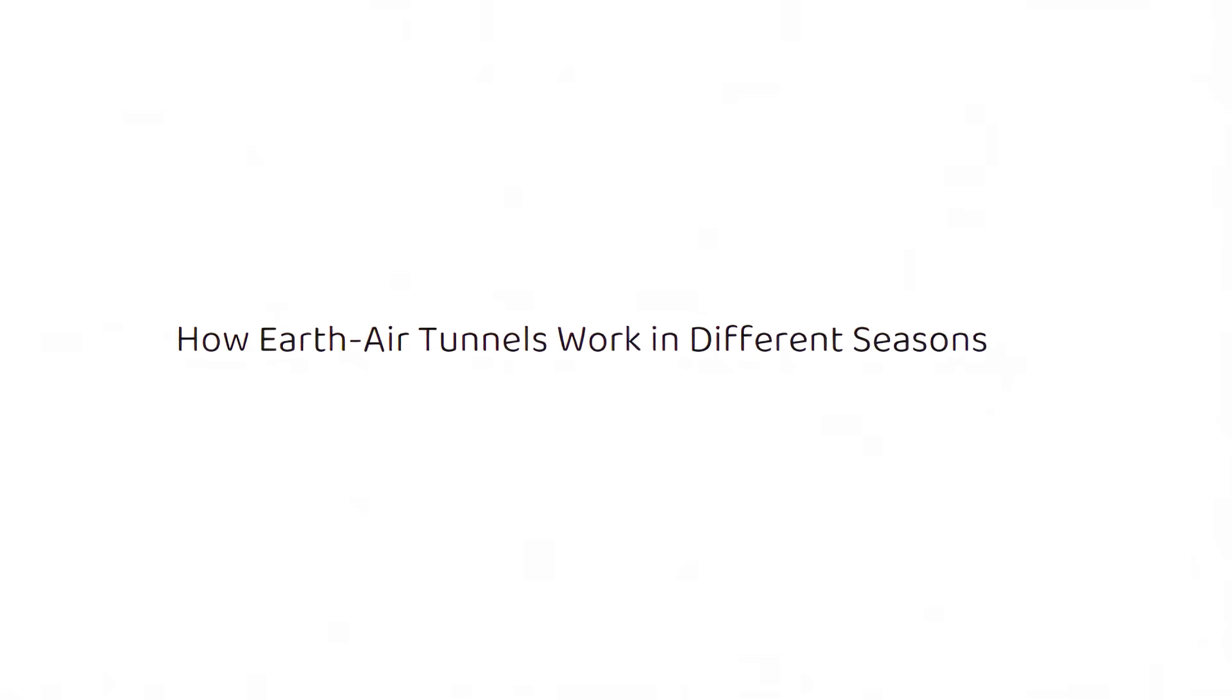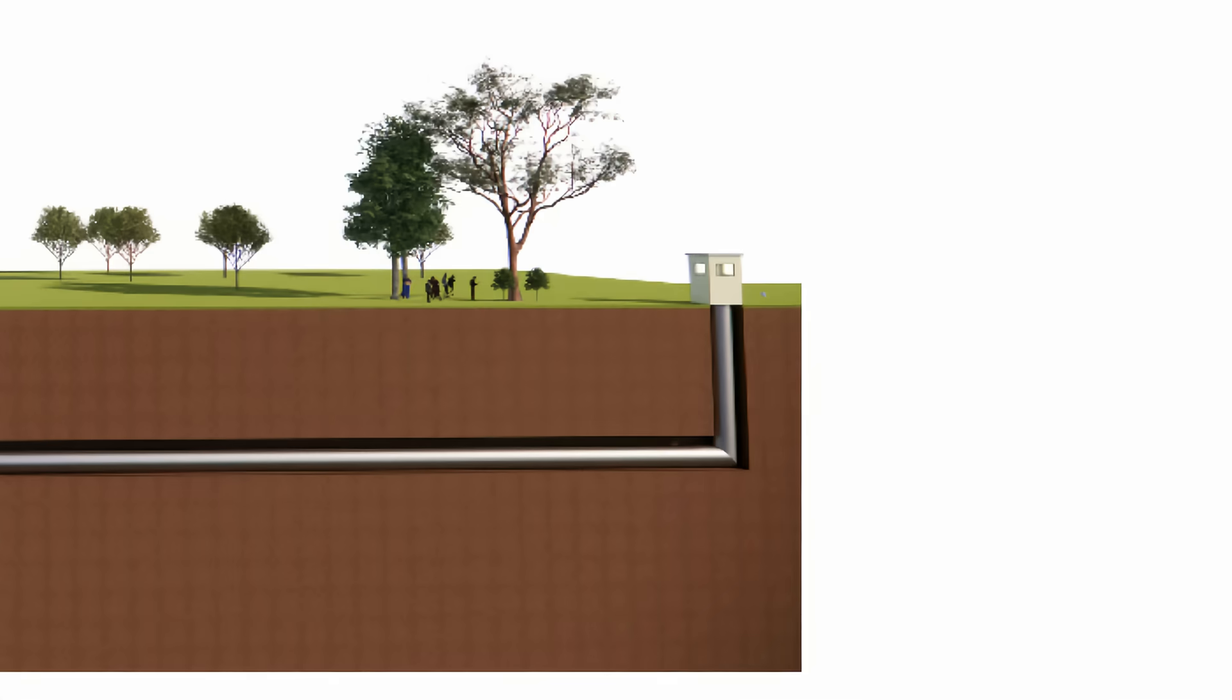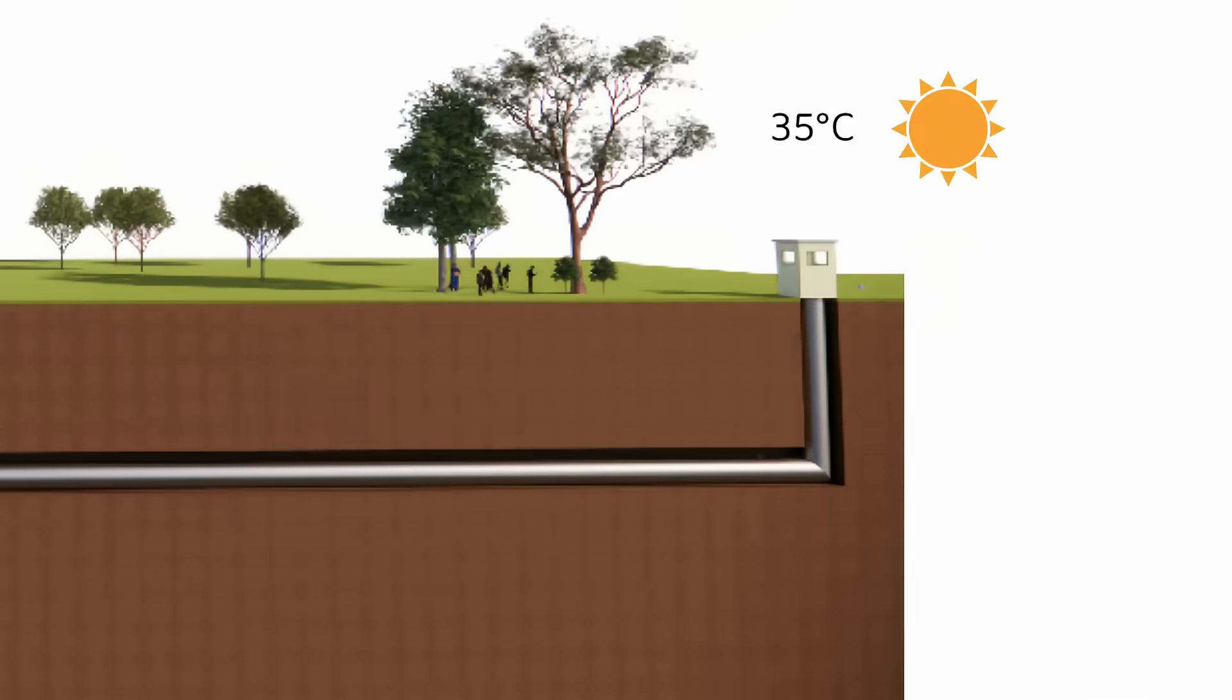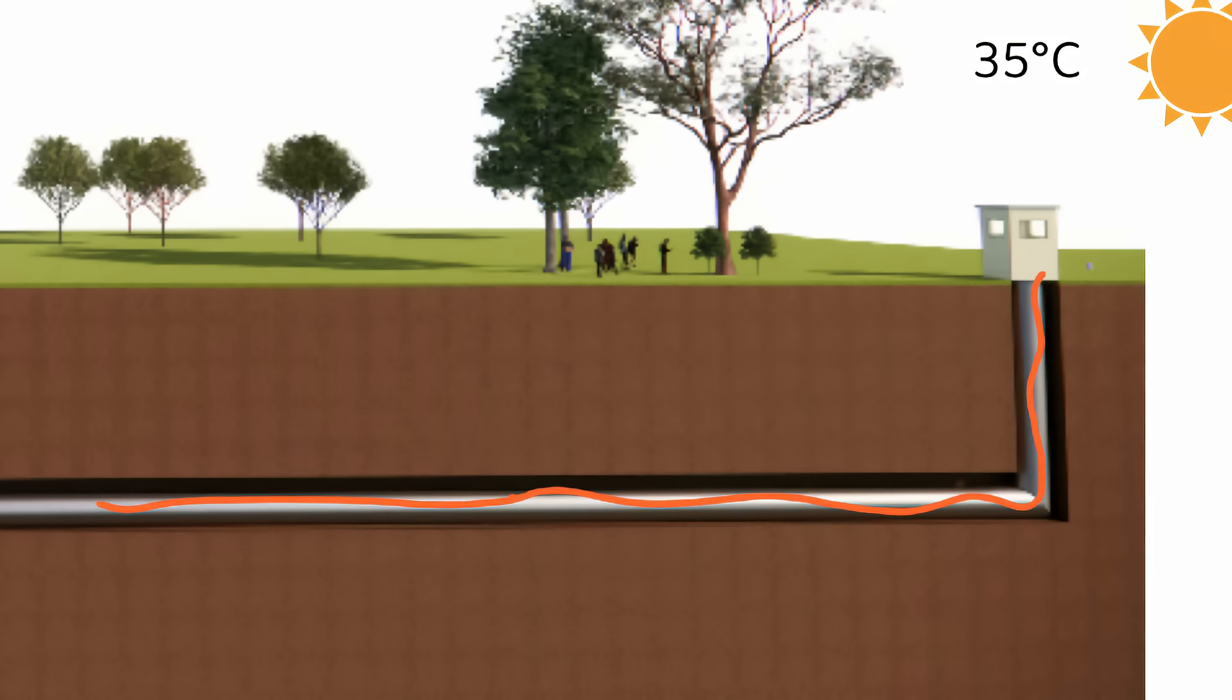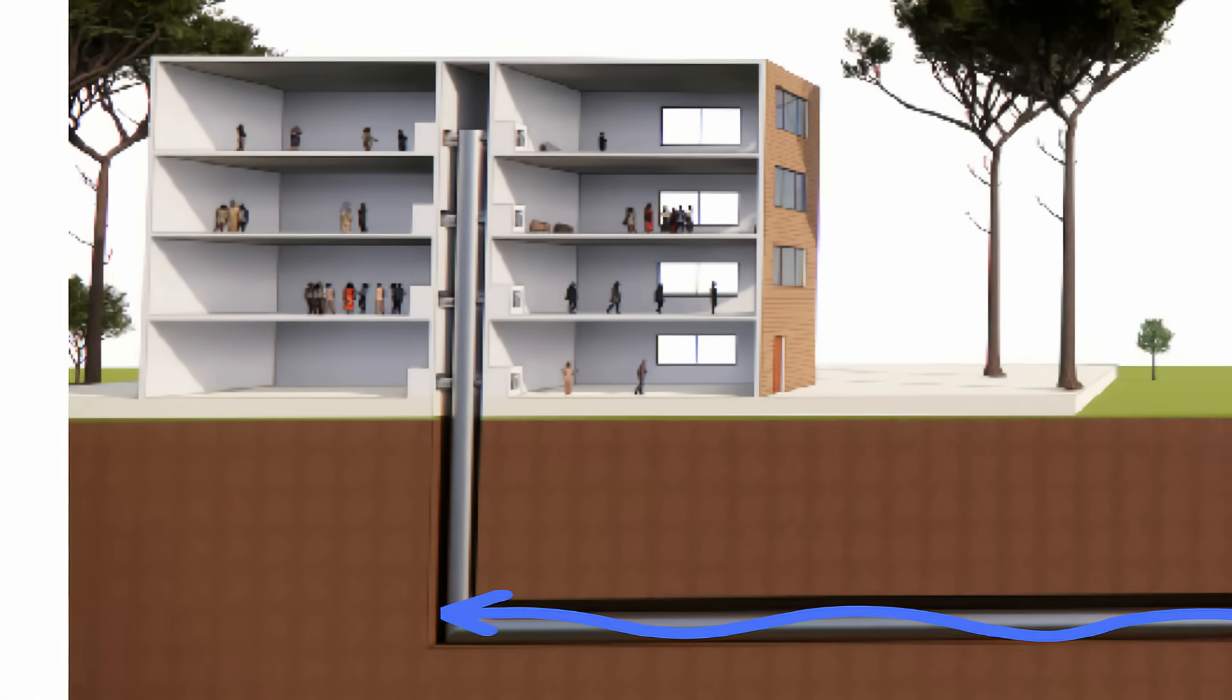How earth-air tunnels work in different seasons. Let's say it's the middle of summer and the outside air is 35 degrees Celsius. Instead of bringing this hot air directly into your home, it first travels through the underground pipes. Since the soil at this depth is 15 degrees Celsius, the hot air transfers its heat to the cooler soil as it moves through the tunnel. By the time the air reaches your home, it has cooled down to a comfortable 18 to 22 degrees Celsius, reducing the need for air conditioning.